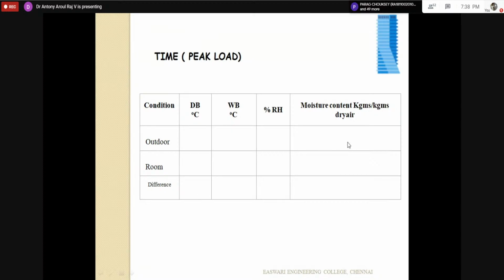Outside the moisture will be higher, in grains per pound or grams per kg. Inside the grams per kg will be smaller; outside the grams per kg is higher. So find the difference and multiply that with latent heat - that will be the latent component, very simple. This difference will give you the sensible component.